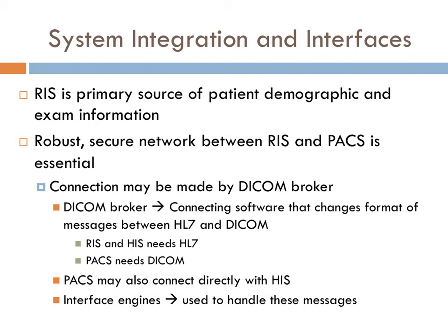It doesn't matter how many systems communicate with each other, but the overall system throughput, so how long it takes for a patient's exam from the time the order is placed until it is archived, must be tested to ensure the data has not changed. As part of the acceptance testing project, and just to understand the interaction of the information at your facility, you should really think about mapping your PACS configuration and all the systems that touch it prior to beginning the actual acceptance testing. I want you to take a look at figure 23.1 of your book for an example.